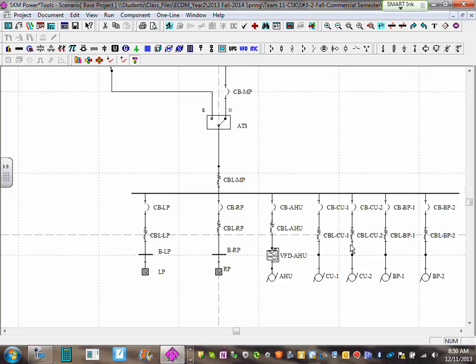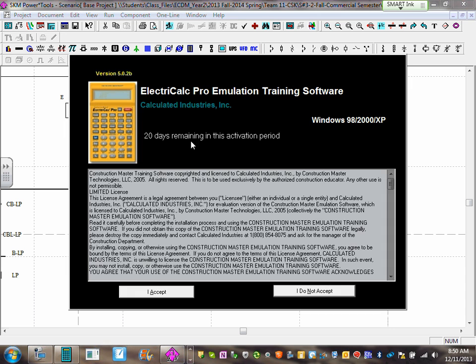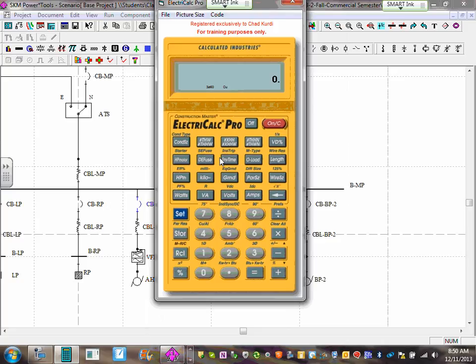I only care about the circuit breakers for the air handling unit, CU1, and CU2. The air handling unit was 15 horsepower at 208V. The inverse-time circuit breaker sizing gives me 115.5 amps, so the next standard size is 125 amps. I need a 125-amp circuit breaker for the air handling unit.